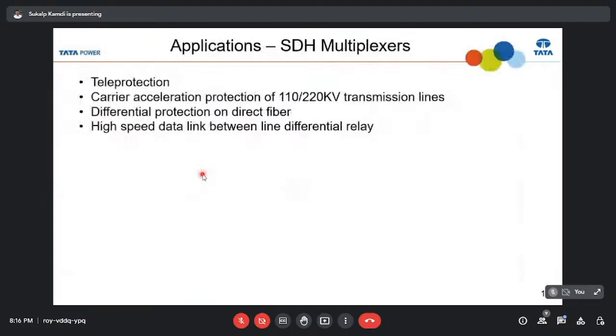What is the SDH multiplexer? As I said, they are used for teleprotection, the carrier protection of 110 kV, 220 kV transmission lines. Now, carrier is basically the term used in electrical utility for communication. Carrier is a medium through which the command of that relay is transmitted from one receiving station, one substation to other substation. So this type of protection is used for the EHV lines.